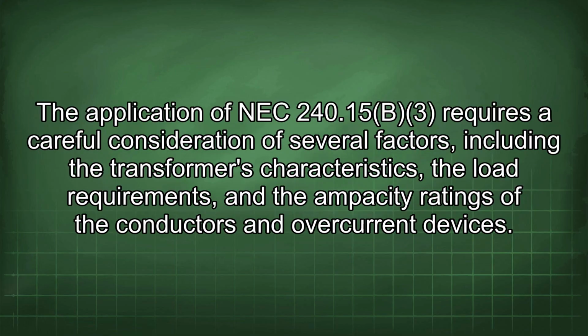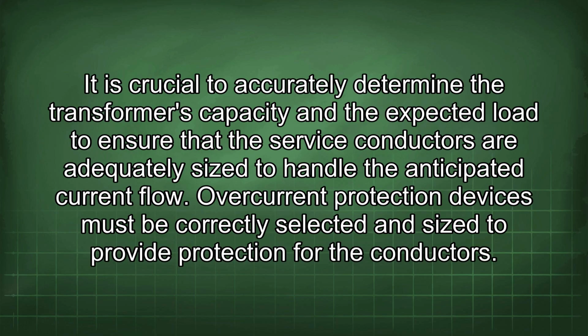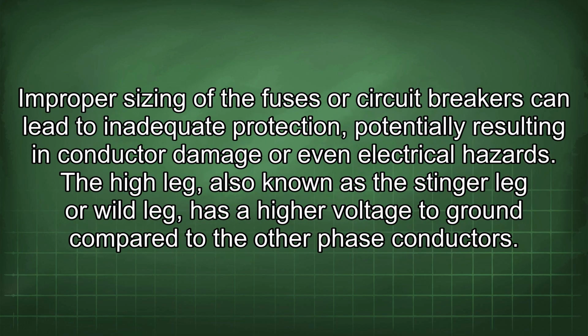The application of NEC 240.15(B)(3) requires a careful consideration of several factors, including the transformer's characteristics, the load requirements, and the ampacity ratings of the conductors and overcurrent devices. It is crucial to accurately determine the transformer's capacity and the expected load to ensure that the service conductors are adequately sized to handle the anticipated current flow. Overcurrent protection devices must be correctly selected and sized to provide protection for the conductors.